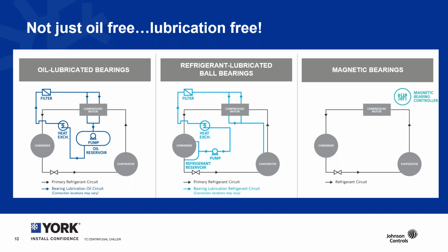There are some design practices that would allow you to use a refrigerant lubricated ball bearing system to eliminate the oil out of the chiller. But if you notice on the chart, a refrigerant lubricated system is equally complex as the oil lubricated system. They simply are using a different lubricant, a lower viscosity lubricant that likes to change its phase from a liquid to a gas. And so in the end, that lubricant's a little less reliable than oil, which is world-renowned as an excellent lubricant. So for magnetic bearing systems, simplicity is the key to offering superior durability.